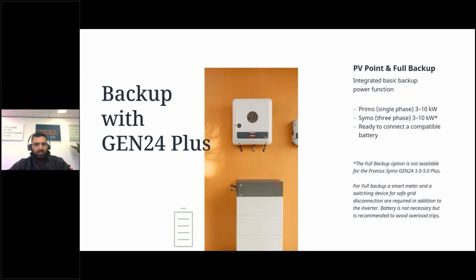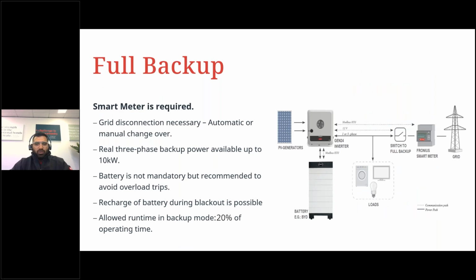So let's move on to the full backup. As we all know, to run the system in full backup, we should not be connected to the grid. So we can either have a manual changeover switch or an automatic one, depending on how you want to do it. One thing is, a battery is not really mandatory to have full backup, but it is recommended to avoid overload trips. And a battery is necessary if full backup is needed at nighttime, because at night we don't have sun. Unlike PV Point, in a system for full backup we must have a smart meter in the feeding point. But please note that the smart meter should be outside the backup circuit. So when the system is running in backup, the smart meter is not power supplied.